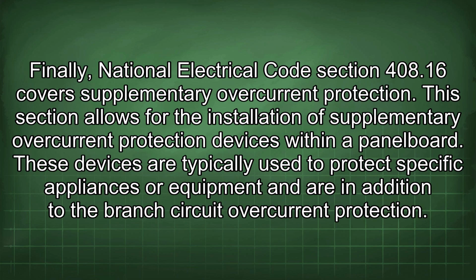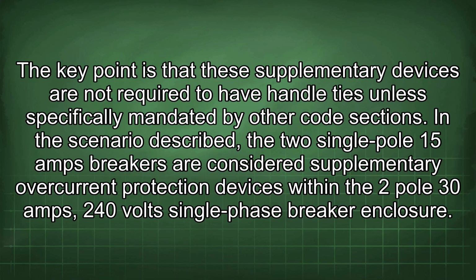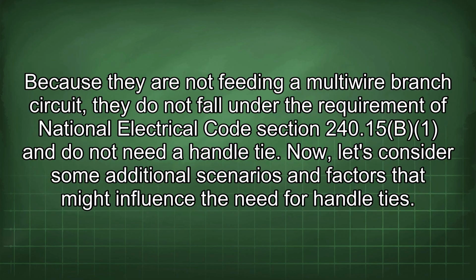Finally, National Electrical Code Section 408.16 covers supplementary overcurrent protection. This section allows for the installation of supplementary overcurrent protection devices within a panel board. These devices are typically used to protect specific appliances or equipment and are in addition to the branch circuit overcurrent protection. The key point is that these supplementary devices are not required to have handle ties unless specifically mandated by other code sections. In the scenario described, the two single-pole 15 amp breakers are considered supplementary overcurrent protection devices within the two-pole 30 amp 240 volt single-phase breaker enclosure. Because they are not feeding a multi-wire branch circuit, they do not fall under the requirement of National Electrical Code Section 240.15(B) and do not need a handle tie.